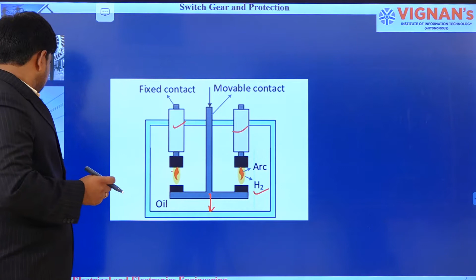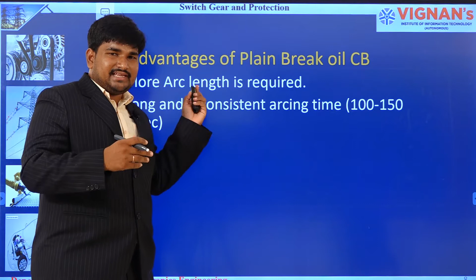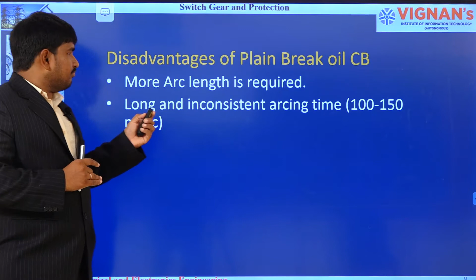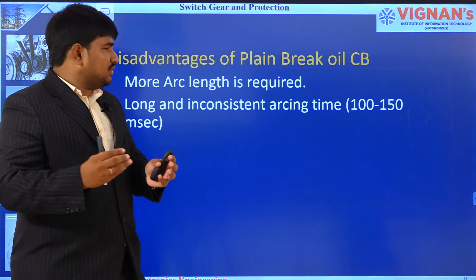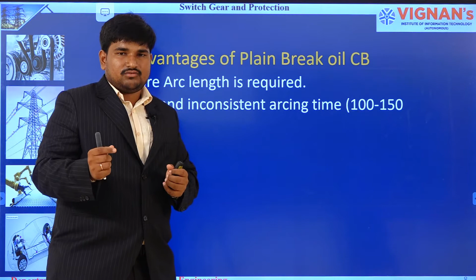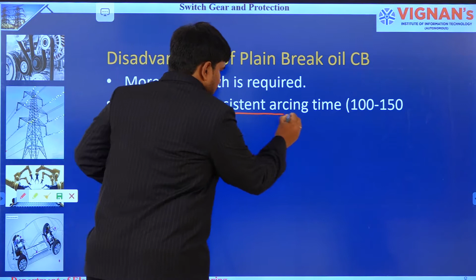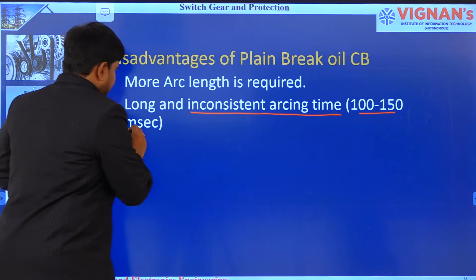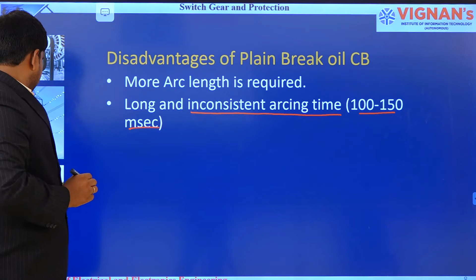If you observe the disadvantages, to increase the voltage we need to increase the arc length, that is, increase the gap. That is one more disadvantage of the plain oil circuit breaker. The next one is inconsistent arc timing. There is no consistent arc timing in the plain oil circuit breaker, because we are providing the arc quenching property just by increasing the gap between the contacts, so there is no confined time to quench the arc. It is about 100 to 150 milliseconds. Now let us go to applications.